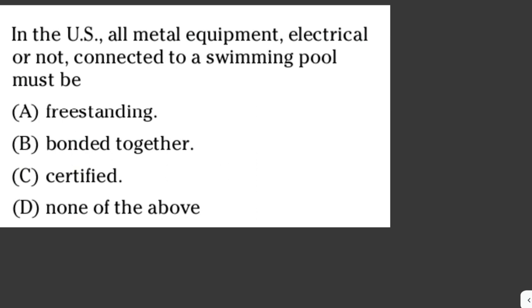In the U.S., all metal equipment, electrical or not, connected to a swimming pool must be bonded together by a minimum of number eight wire for safety purposes. That includes the heaters, pumps, stairs, diving boards, railings, rebars, and other things.